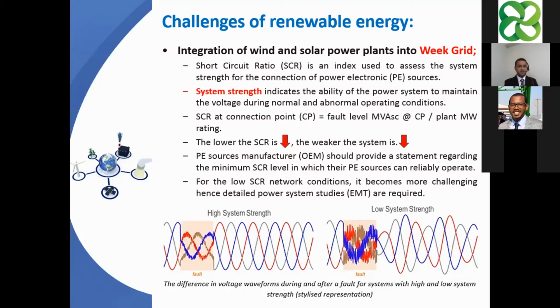So the risk here is that a low short circuit network condition becomes more challenging, and hence we need to do detailed power system modeling and studies, which we call EMT or electromagnetic transient analysis. As you can see here, we have two waveforms, both for the event of a fault. The left one is a representation of high system strength, and you can see the waveform during the fault is pretty much stable. But for the low system strength, the voltage waveform is really distorted. So there is a high chance that the system may not be able to operate properly during the fault events, and that may lead to a wide blackout.